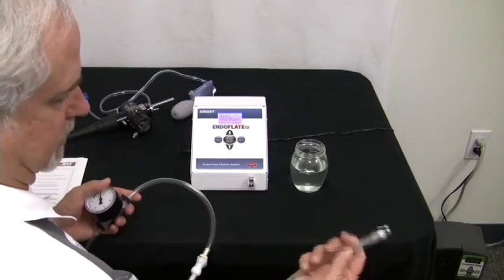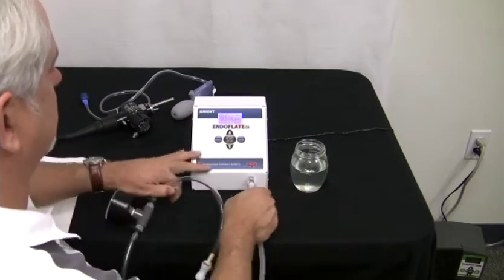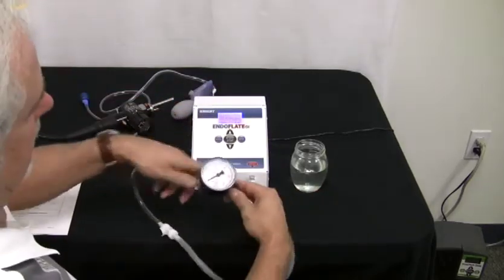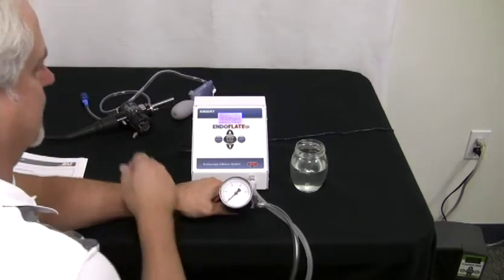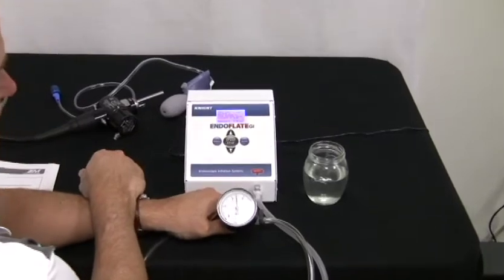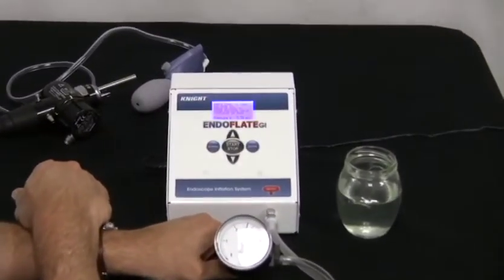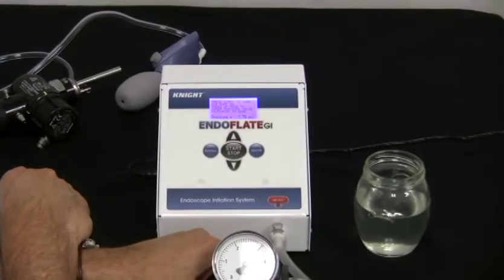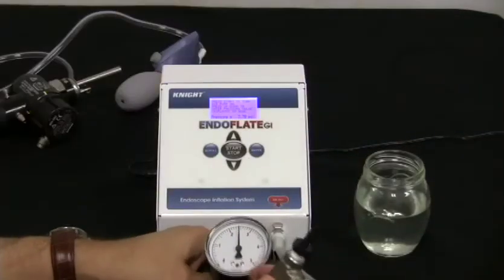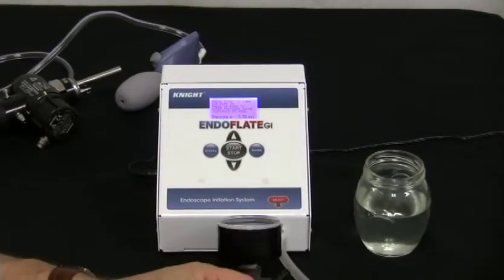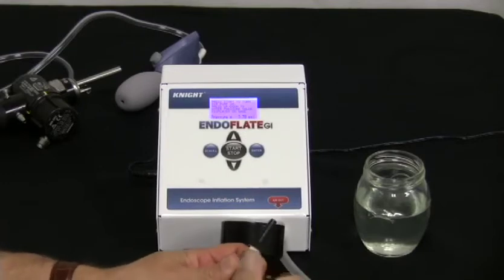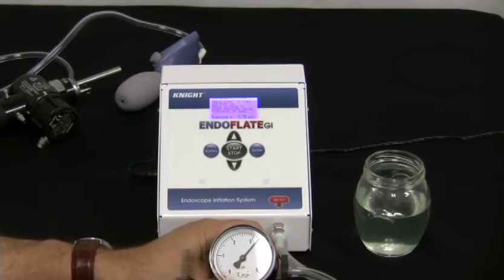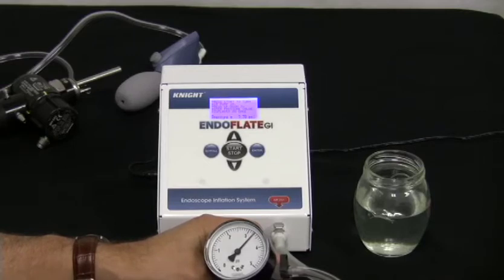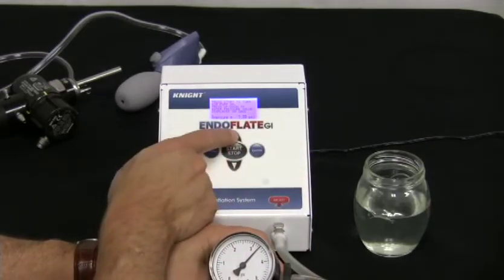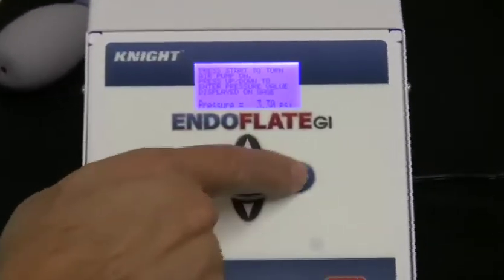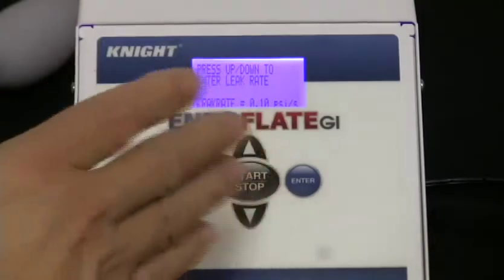So I'm going to take a tube that has the same connector on it as our leak test kit. I'm going to plug it in. On the other end of it, I've got a gauge. Well, it looks like that. And I'm going to hit the start button. And you can see the needle rise and fall. And I can see that right now my valve on the other end is open. I just happen to have a valve here I'm going to use for another demonstration in a minute. I'm going to close that off to simulate a deadhead condition. And you can see now that my needle is stable, and I'm at about 3.3 psi. So that's what I'm going to enter here. I just hit the up button until I get to 3.3. Hit enter, and now the system pressurizes and holds that value. Okay?